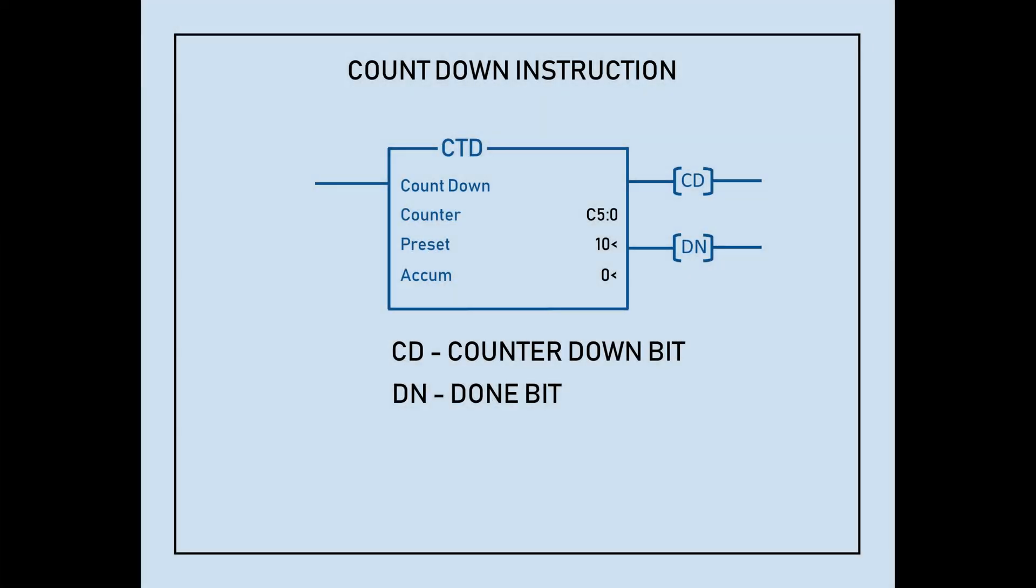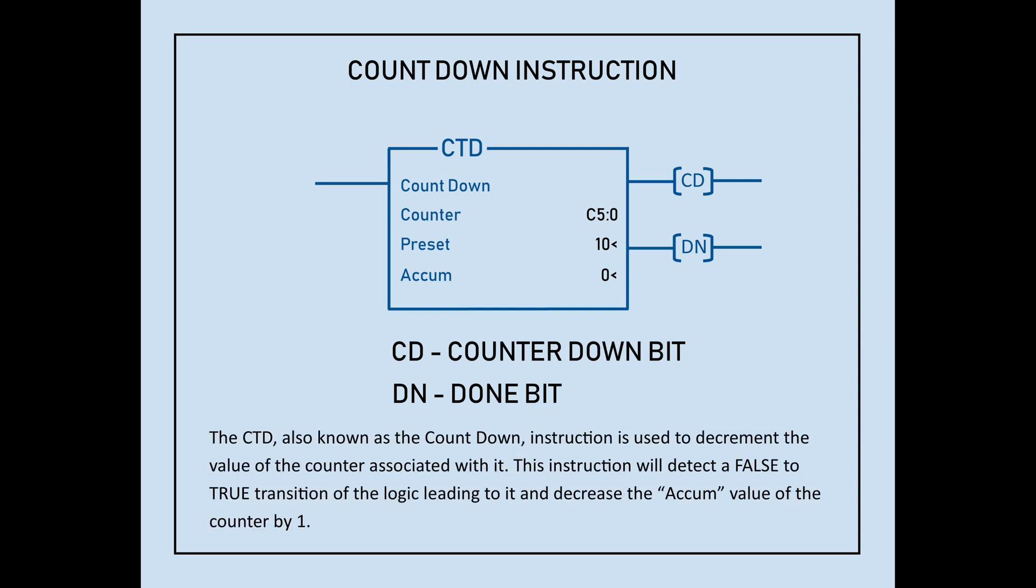The CTD, also known as the Count Down instruction, is used to decrement the value of the counter associated with it. This instruction will detect a false to true transition of the logic leading to it and decrease the accumulated value of the counter by 1. The effect of using this instruction is the exact opposite of what the CTU instruction does to the counter.